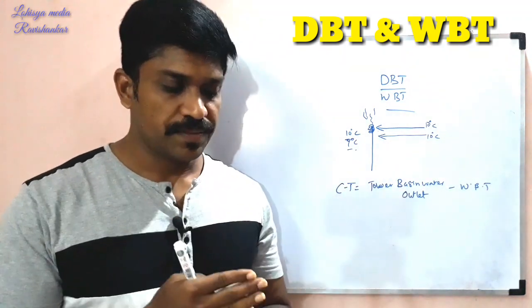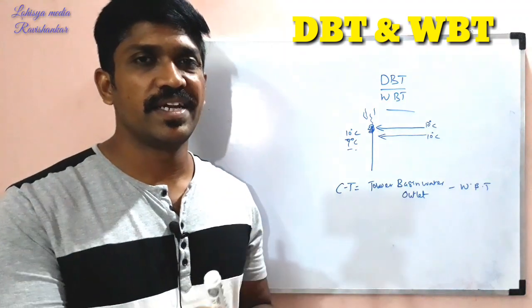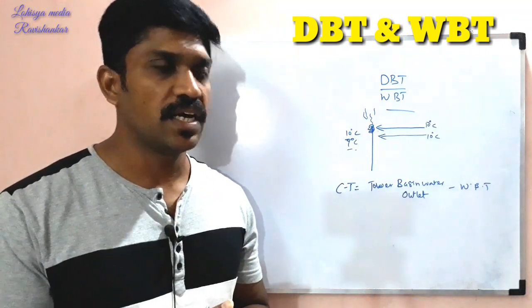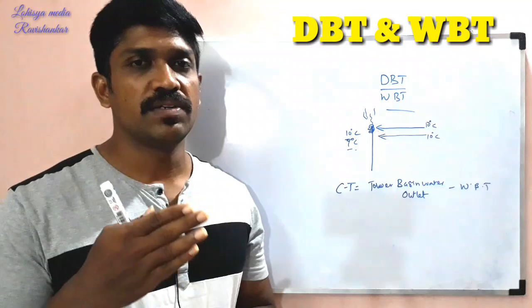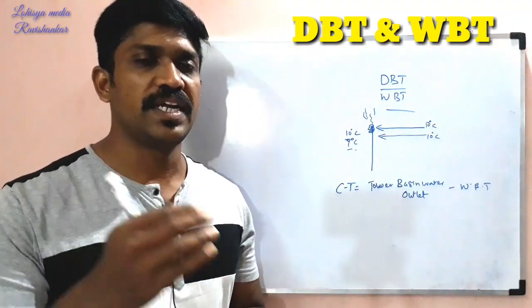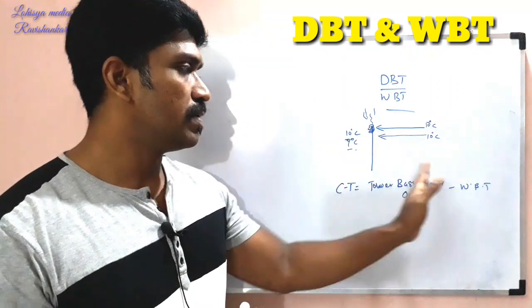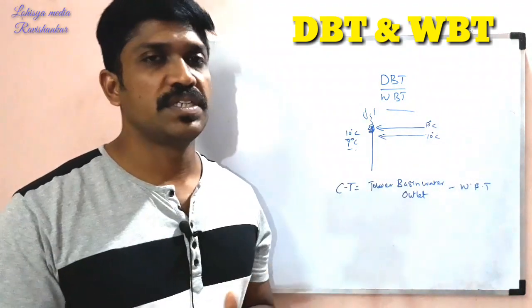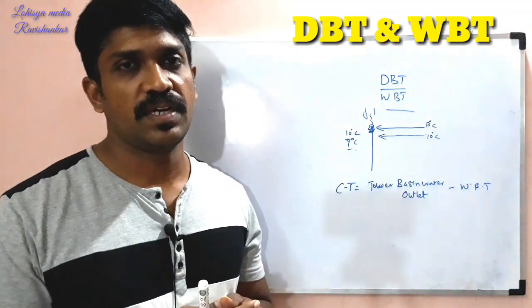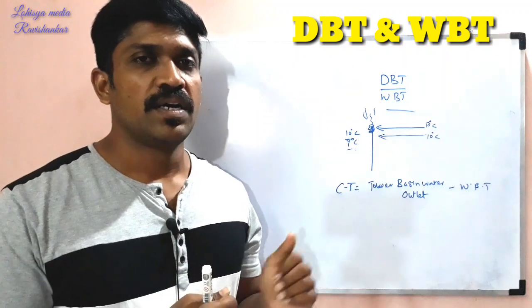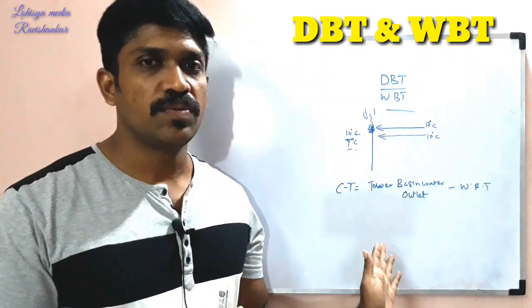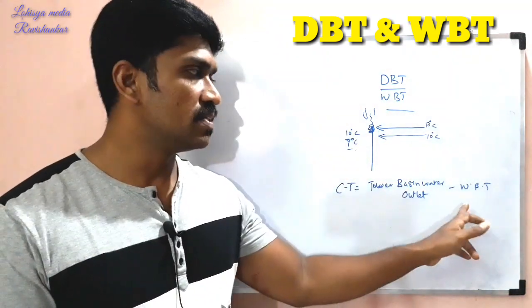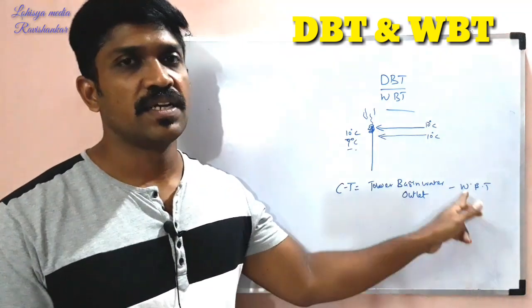Normally, the wet bulb temperature is 28 or 29 degrees. The dry bulb temperature is 33 to 35 degrees, and the wet bulb temperature is 26 to 28 degrees — the night is slightly different. This is the wet bulb temperature. What we need to do is determine the cooling tower approach. The wet bulb temperature is very important for designing cooling towers.